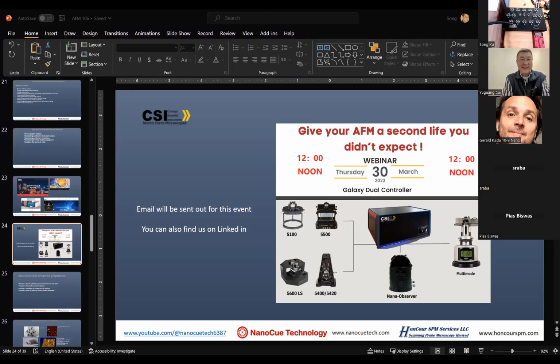Steve, when you say two different revisions, are you talking about the AC box or the controller? The head electronics box. I see. So one of them has a little calculation somewhere, right? Yes. The older head electronics boxes that were produced, I want to say somewhere around 2008 to 2010, have a different algorithm in the summing signals inside the head electronics box, and there is a 4.3 times gain tied to those signals that newer version head electronics boxes don't have.